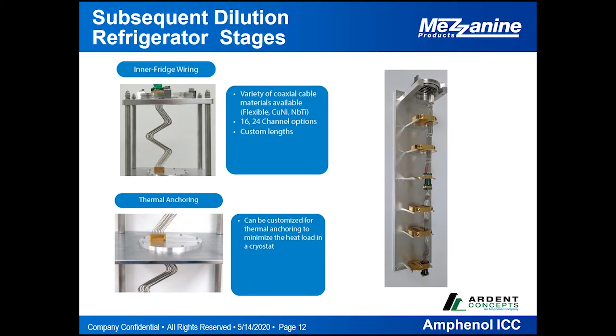From a cable and non-magnetic standpoint, as I mentioned, Ardent offers multiple form factors of our product and varying degrees of non-magnetic options. So depending on the tolerance of magnetism that your system can handle, we can start to swap out certain materials within the multi-coax connector to reduce the magnetism. So you can see here we have a column which has our standard TR materials on the left-hand side, and then varying degrees of removing magnetics throughout the system. So we have three different M1, M2, and M3 tiers, which allow us to make the connector and the TR multi-coax fully non-magnetic.